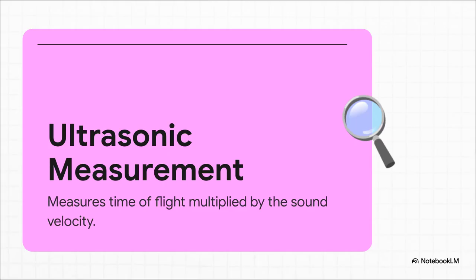And this idea brilliantly illustrates our core magic here. You see, ultrasonic thickness measurement isn't about physical rulers or tape measures. It's all about timing. We send an invisible pulse of high-frequency sound straight into a material, wait for it to hit the back wall, and then time exactly how long it takes to bounce back to us. That is what we call the time of flight. We then multiply that time by the known speed of sound through that specific material. It's essentially echolocation, just like a bat, but we're doing it through solid steel.